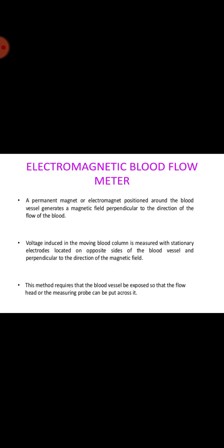The most commonly used type of implantable magnetic blood flow probe has a slip-on or C-type design, applied by squeezing an exposed blood vessel together and slipping it through the slot of the probe. In some transducer models, the slot is then closed by inserting a keystone-shaped segment of plastic, and the contact is provided by two slightly protruding platinum discs that touch the wall of the blood vessel.